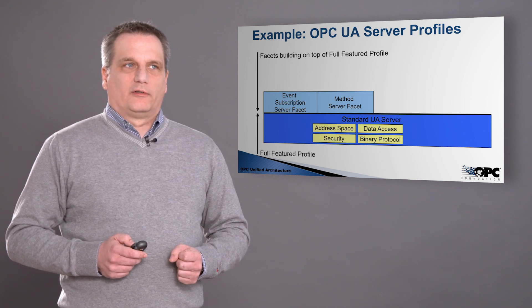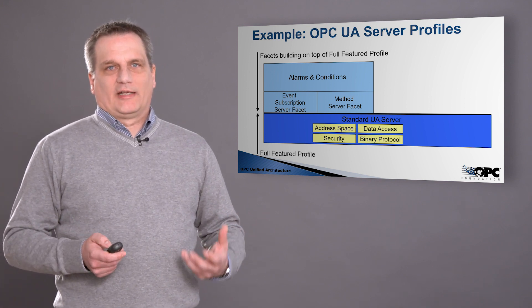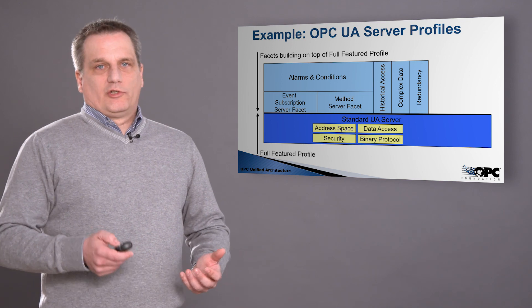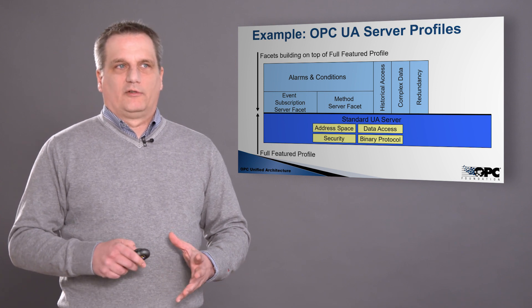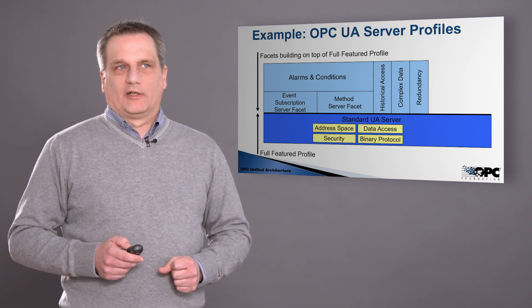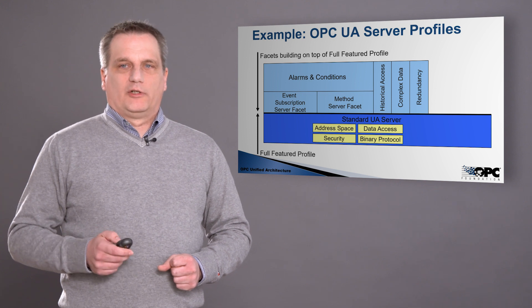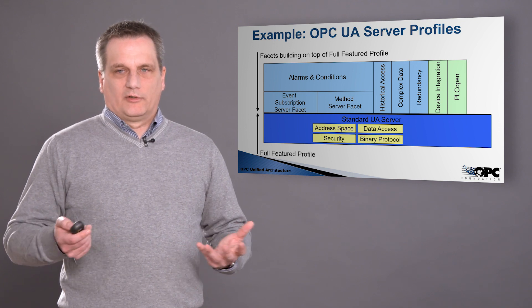The two together give us alarms and conditions. So this would be a standard UA server that has alarms and conditions capabilities — we can have an event and with the method we can acknowledge this event. In addition to that, the server can be extended with a historical access and with a complex data or redundancy facet. The server can also be extended with the device information model, the PLC open information model, or any other kind of companion specification model.